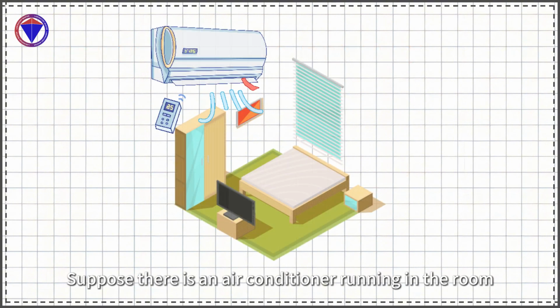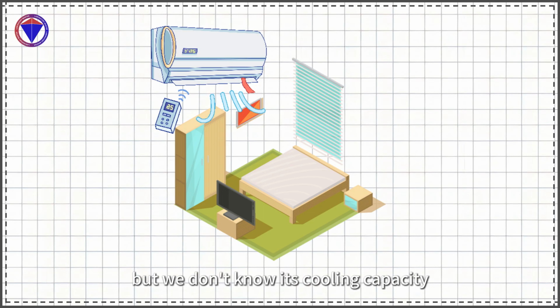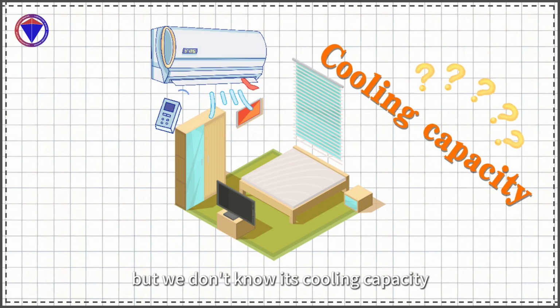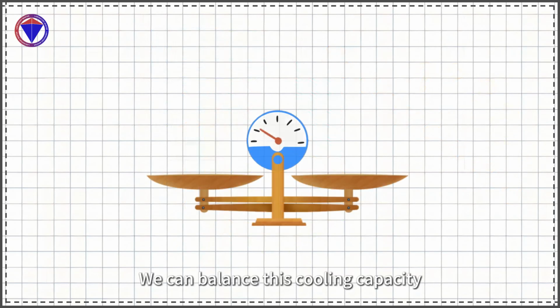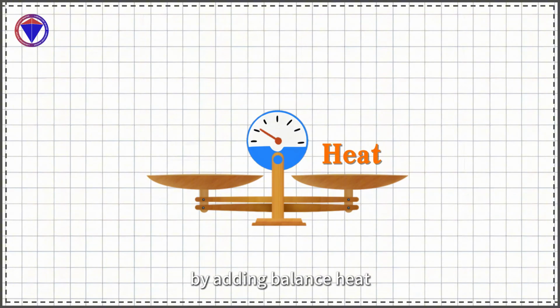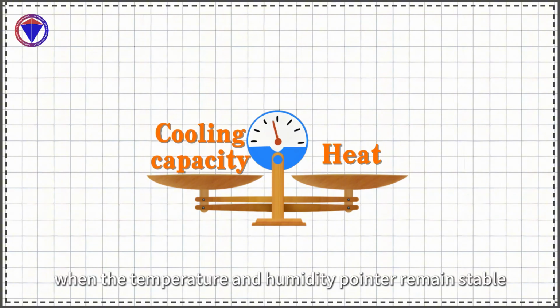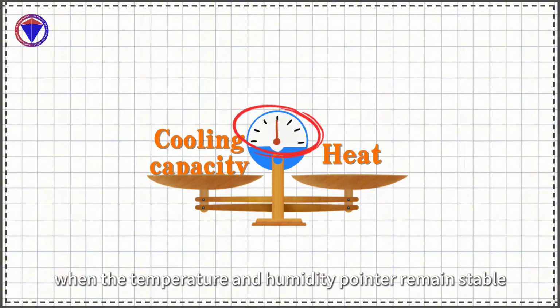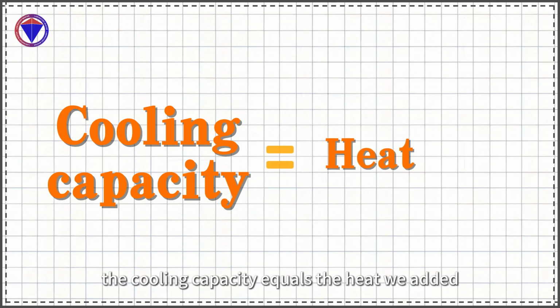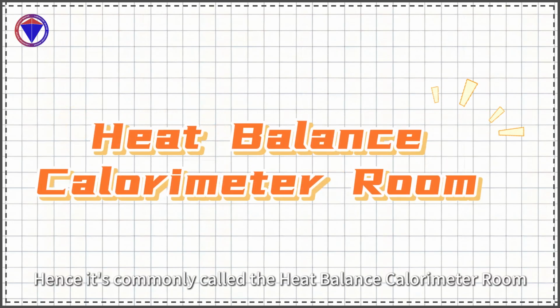Suppose there is an air conditioner running in the room, but we don't know its cooling capacity. How can we measure it? We can balance this cooling capacity by adding balance heat until the temperature and humidity pointer remain stable. We can conclude that the cooling capacity equals the heat we added as a balance weight. Hence, it's commonly called the Heat Balance Calorimeter Room.